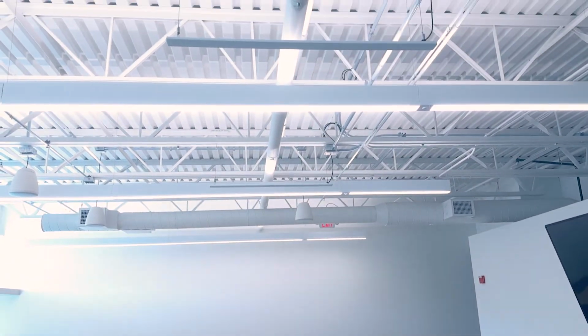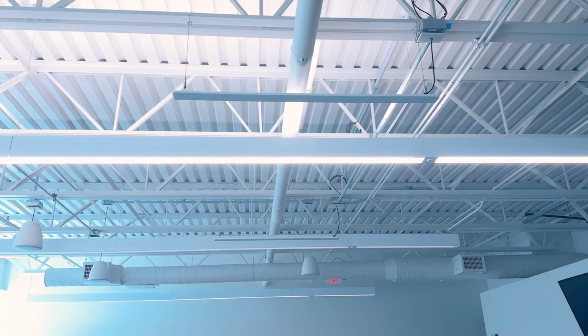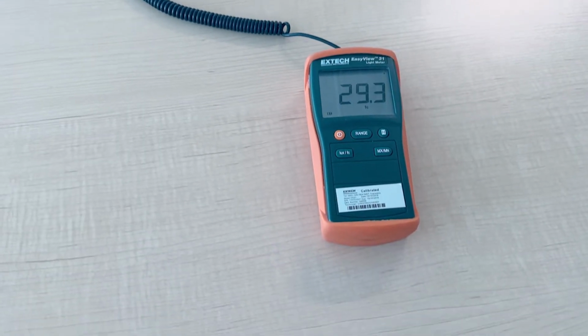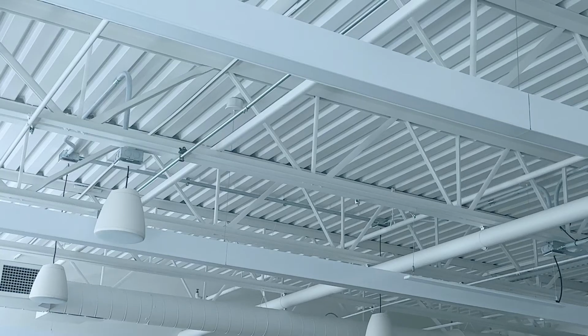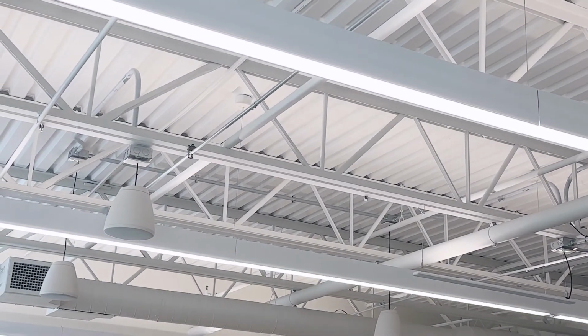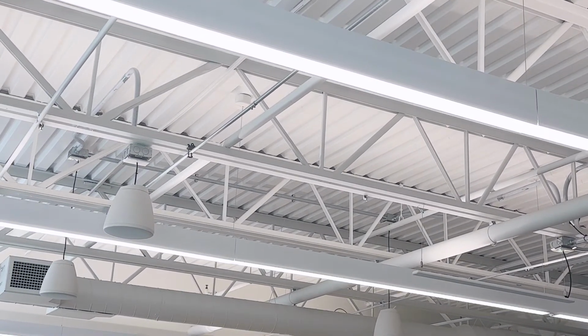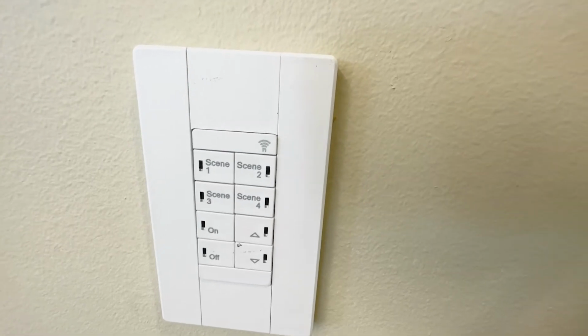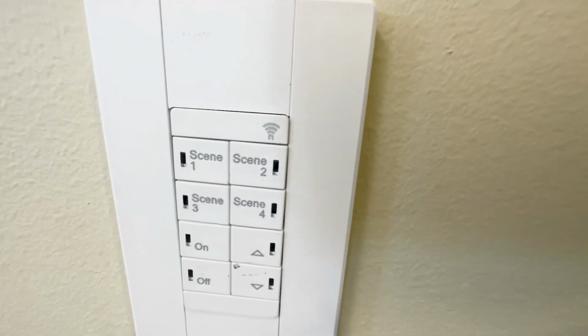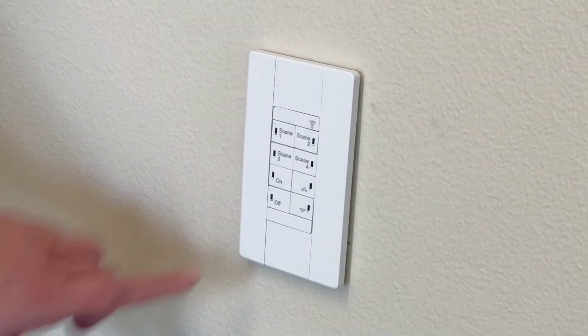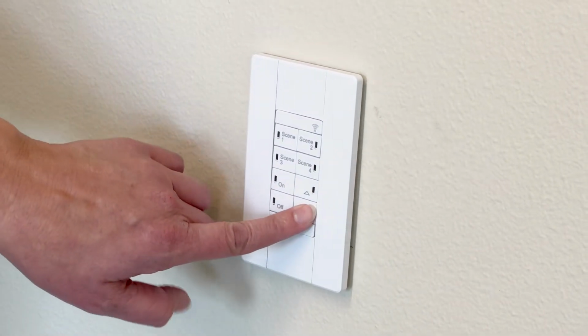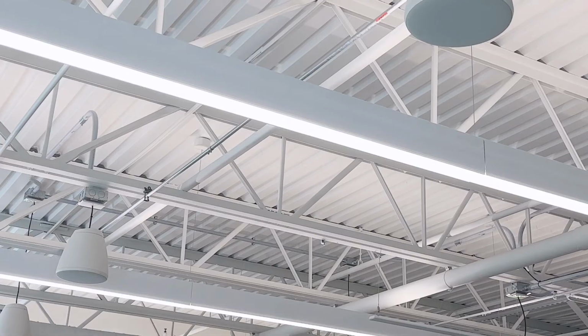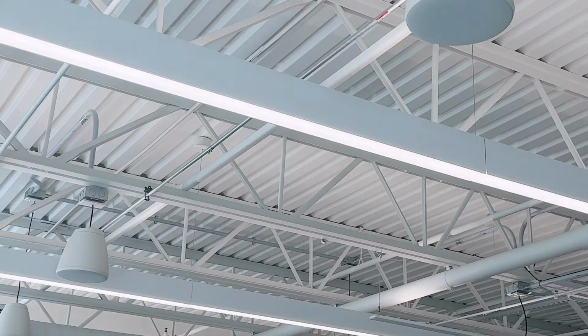capability to implement other advanced lighting control strategies, such as task tuning via high-end trim adjustment, minimizing the risk of glare due to overlit spaces, particularly in retrofit applications. Wireless luminaire level lighting controls, or LLLCs, reduce or eliminate the need for low voltage control wiring, which can offset higher upfront fixture costs.